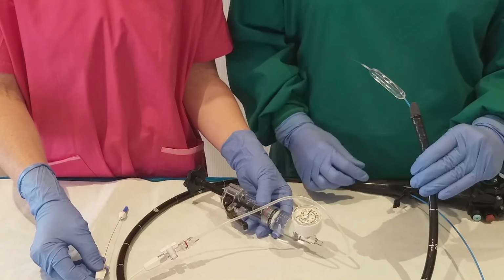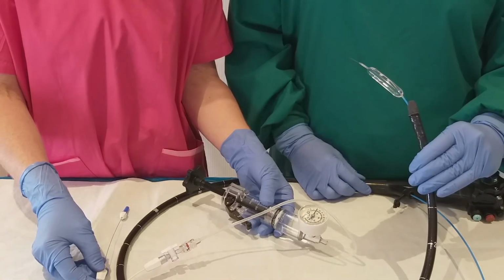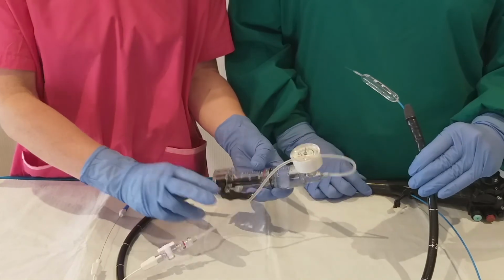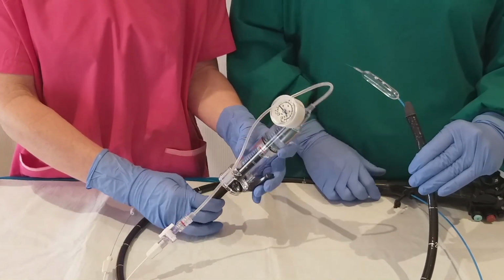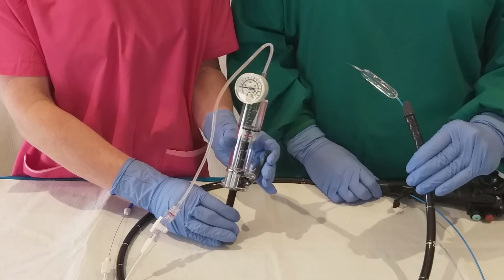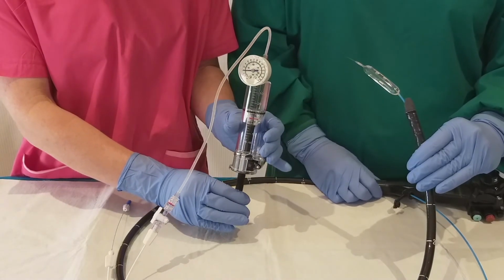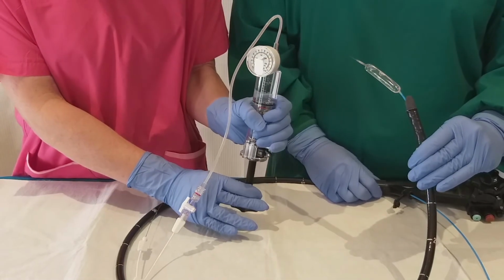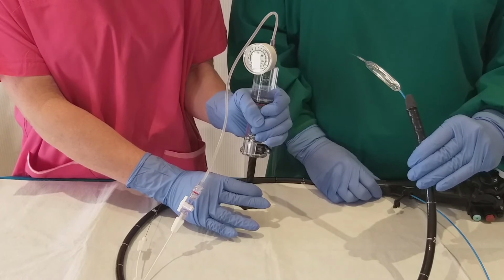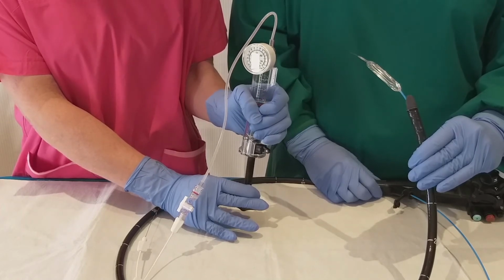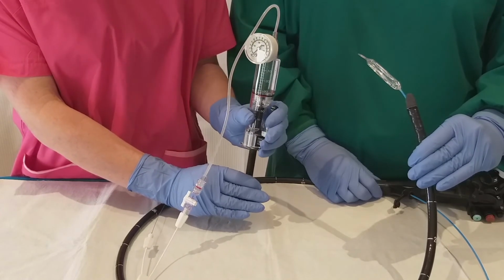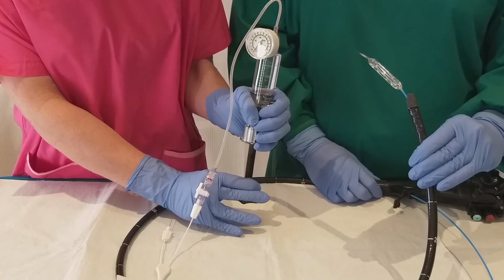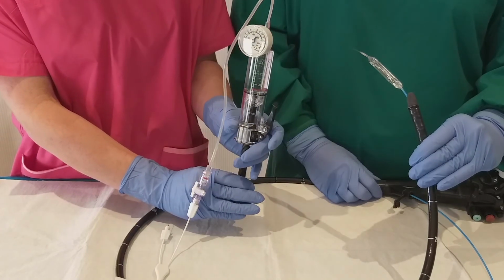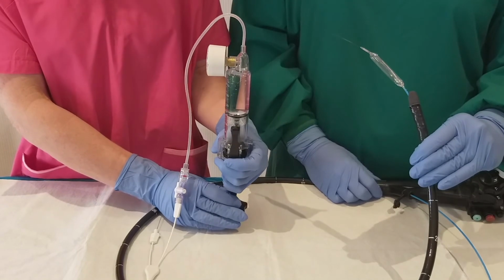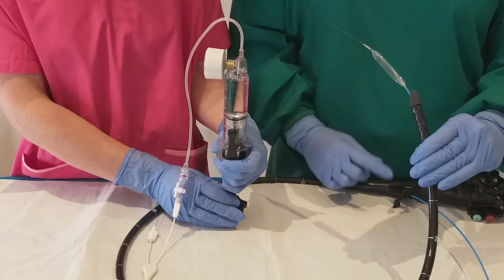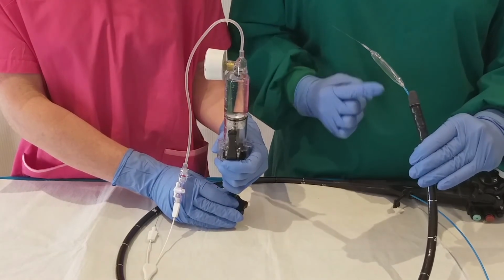To remove the catheter, you firstly need to deflate the balloon. This is done by applying negative pressure with the inflation device. To deflate the balloon quickly, squeeze the lever and pull down firmly on the syringe while facing it upwards until you pass the 35 ml marker, the red arrow. Release the lever. Water will continue to drain into the syringe without applying excessive force. Ensure all liquid is withdrawn from the balloon before slowly removing the catheter from the endoscope.